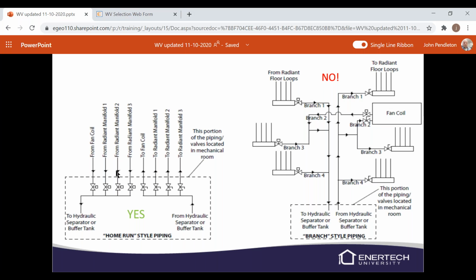We do recommend home run style piping. What we mean by home run style is all the valves and controls and where they end up all come back to the mechanical room. If you put the zone valves at the unit, then you're going to have to get to those units to see if they're open or closed. When you're flushing, it's going to be a pain, especially if they're in an attic or a crawl space. You really don't want to be crawling in and out of there all day checking things. So if they're in the mechanical room and you're working at the unit, then you can walk right over to it and see if the zone control is open. So it's a lot easier to troubleshoot and to flush if all the controls and such are in the mechanical room back by the unit. So we do recommend the home run style. We do not recommend the branch style. You can do what you want. These are recommendations, but it's going to make it a lot easier for everybody if you do the home run style piping.